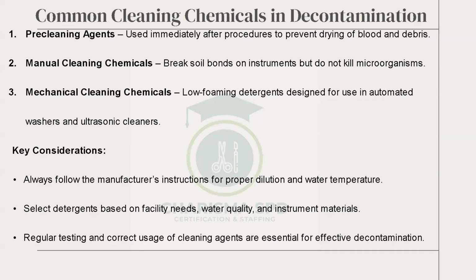Common cleaning chemicals in decontamination, the pre-cleaning agents. Who is going to take this slide? Common cleaning chemicals in decontamination. Pre-cleaning agents used immediately after procedures to prevent drying of blood and debris. Manual cleaning chemicals break soil bonds on instruments but do not kill microorganisms. Mechanical cleaning chemicals, low foaming detergent designed for the use of automated washers and ultrasonic cleaners. Key consideration, always follow the manufacturer's instruction for proper dilution and water temperature. Select detergent based on facility needs, water quality, and instrument materials. Regular testing and correct usage of cleaning agents are essential for effective decontamination.